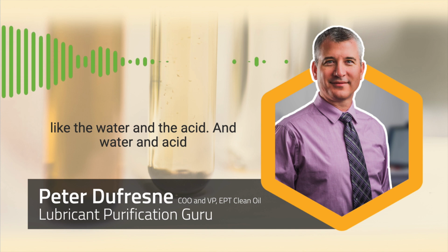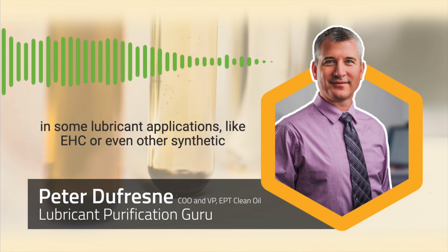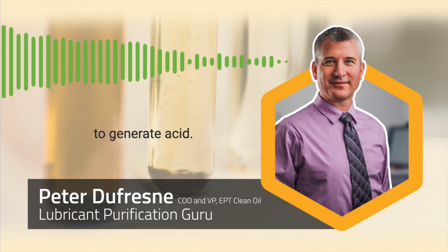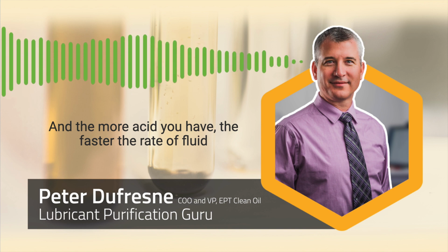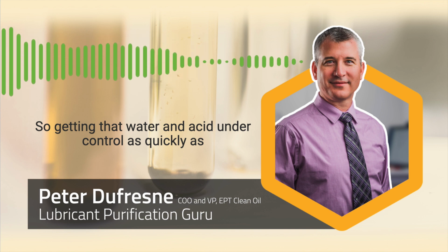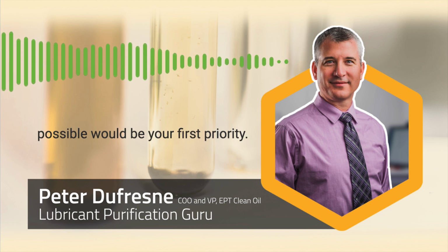And water and acid in some lubricant applications, like EHC or even other synthetic fluids, they're very susceptible to water, which is going to generate acid. And the more acid you have, the faster the rate of fluid breakdown occurs. So getting that water and acid under control as quickly as possible would be your first priority.